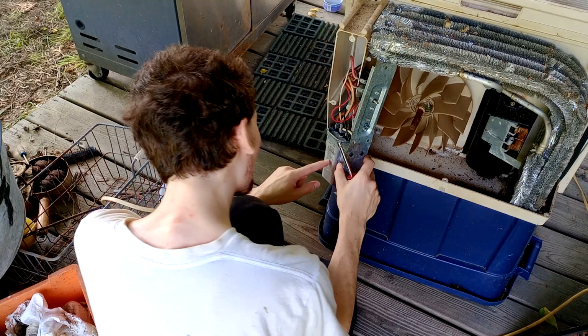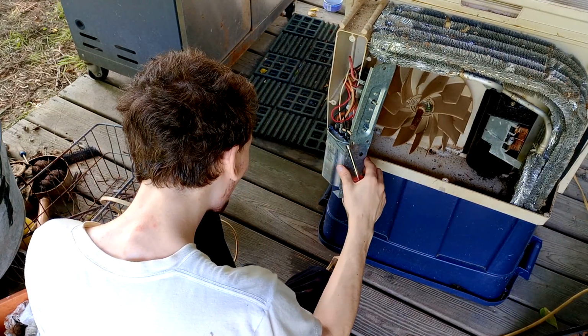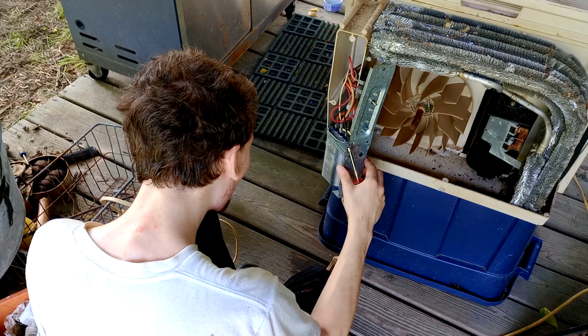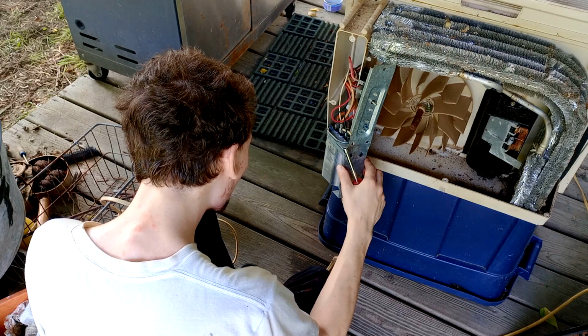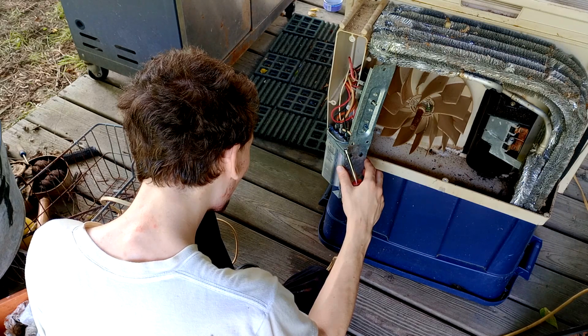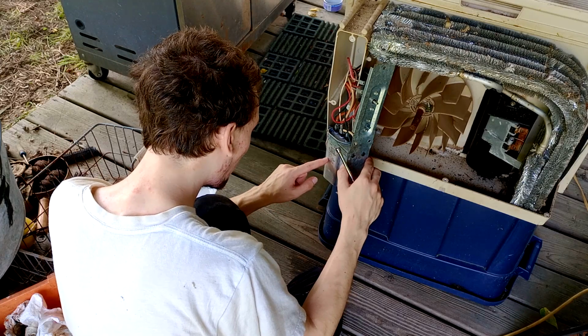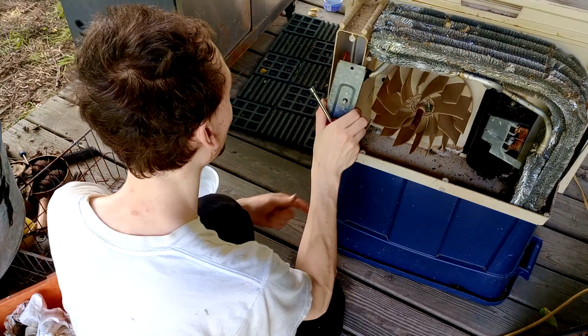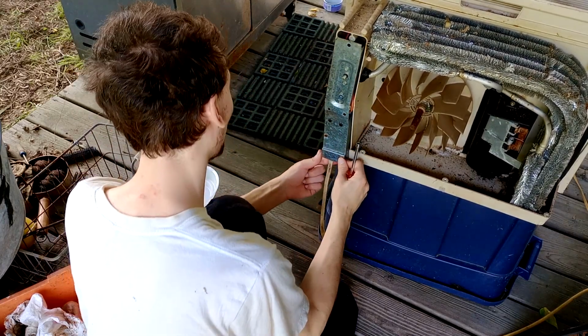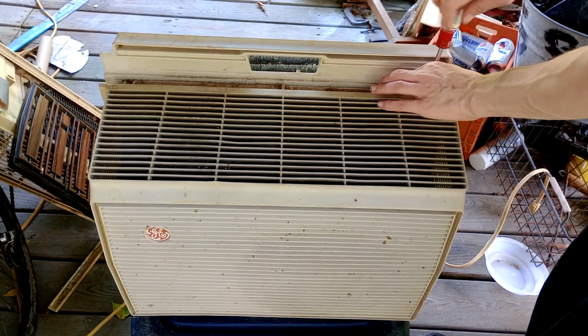Okay. It's a General Electric, made in Mexico, dielectric, no PCBs capacitor. It's a 25 UF and a 7.5 UF, 370 volts AC. Okay, I'm just gonna put that back in. It looks fine. Let's get our back off now and inspect the inside of there.